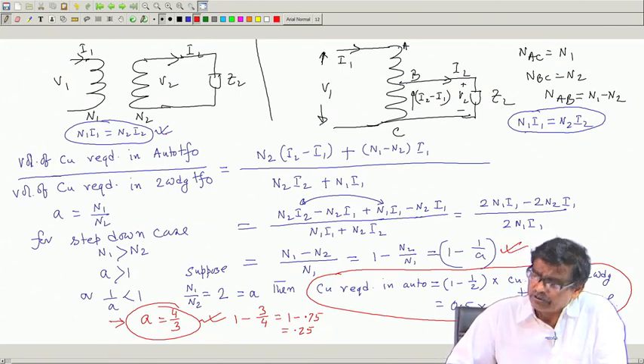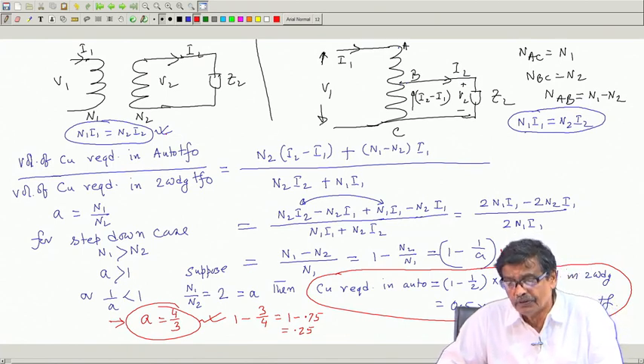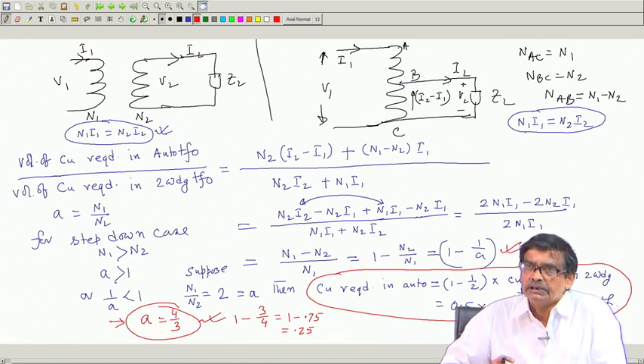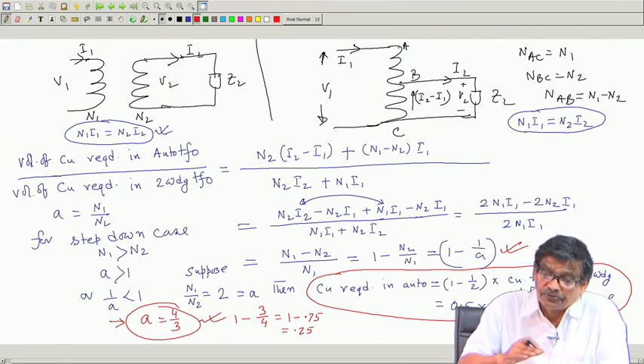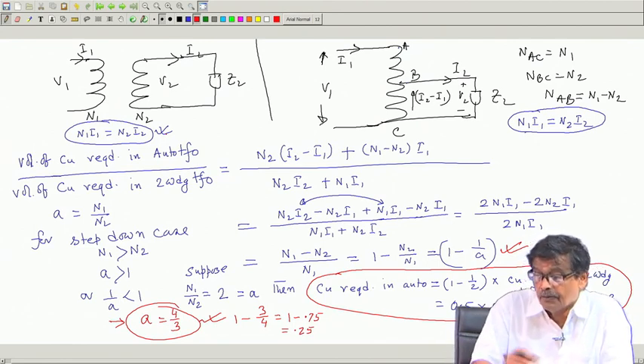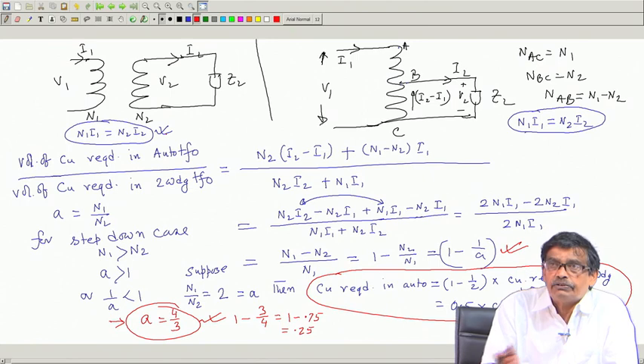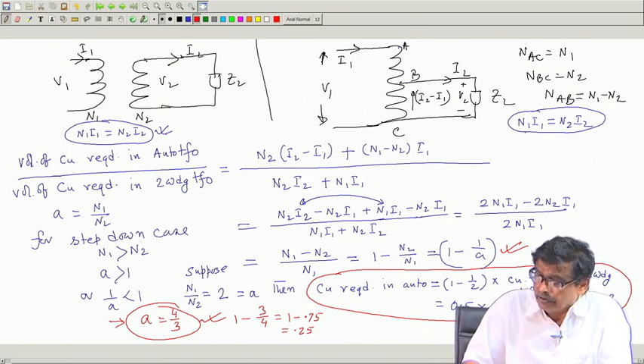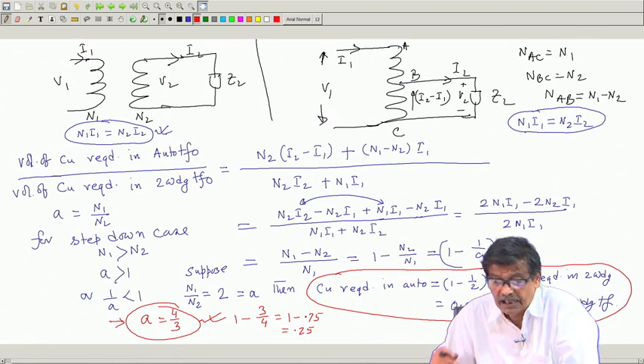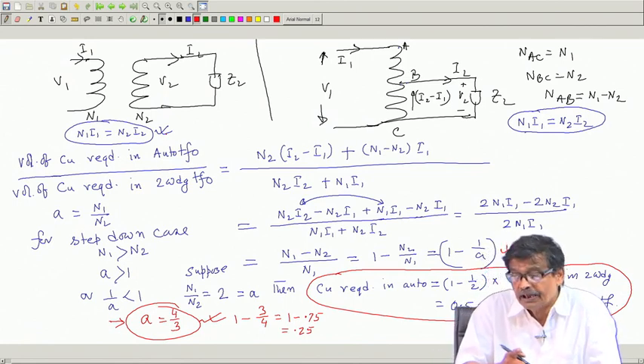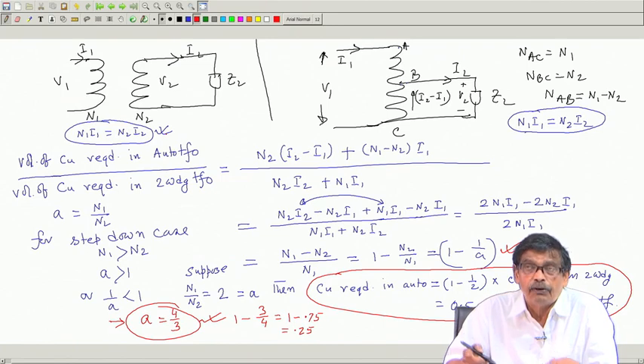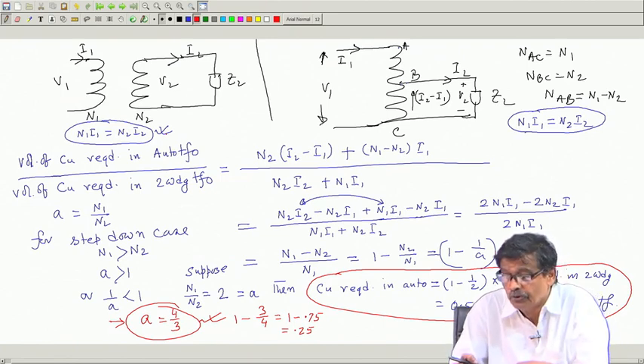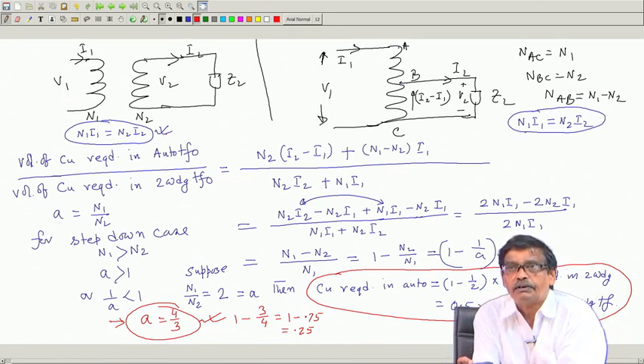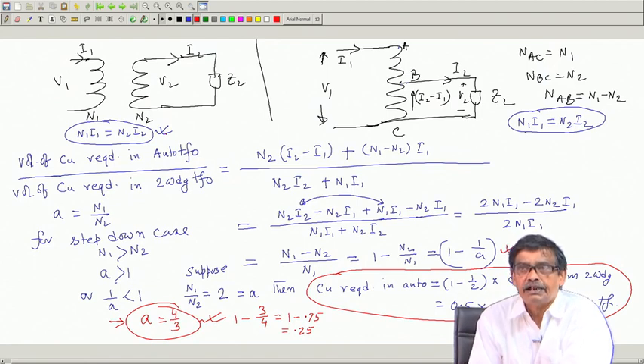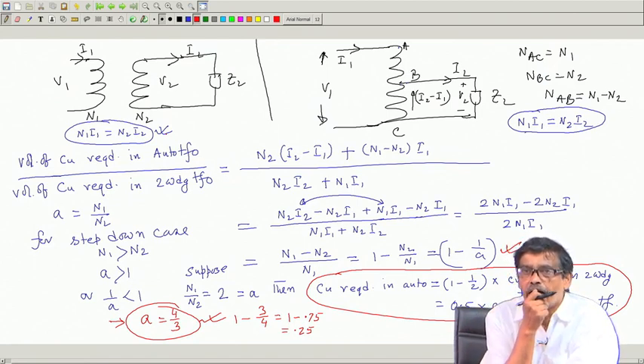It looks like savings of copper will be there in an auto transformer of the same rating compared to a two winding transformer, transmitting the same KVA at the same voltage ratios.